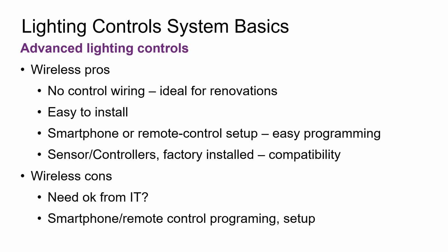The pros of wireless controls is, of course, no wiring is required. This can be especially beneficial for renovations. Compatibility is often no issue as the sensors and controllers are factory installed. The systems are easy to install. Commissioning and programming can be done with smartphone or remote control.